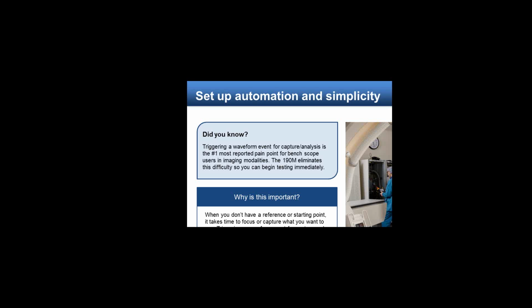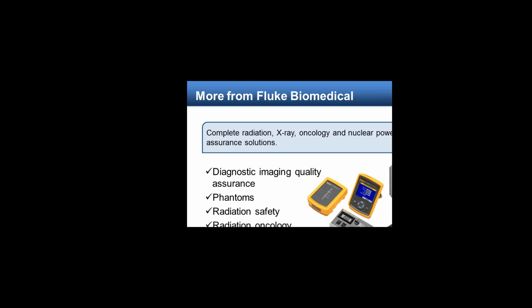But with Connect and View, as I said before, all you need to do is connect up to your reference point, put your probe on the test point, and your waveform is captured right on the screen. The only time you might need to do any manual adjustment of the trigger is if you have a really short duration pulse or wave shape that's kind of inside the Connect and View window capability, and even then you're able to get that waveform on the screen so much faster than you could with any other oscilloscope. So you're really able to get to the analysis and the root cause assessment of your troubleshooting faster with the 190M.